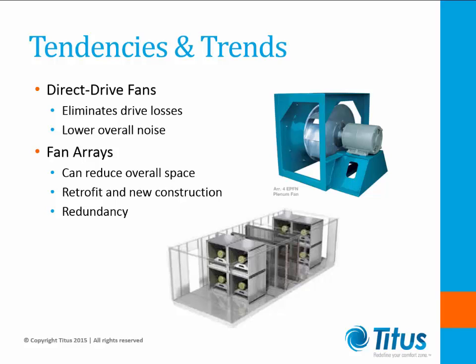In designs that require full fan redundancy, 4-fan systems should be used to keep efficiency high while maintaining a full redundancy requirement. The advantages of selecting fewer, larger fans and motors will dramatically reduce the life cycle cost of owning and operating the air handling units while maximizing the system uptime.